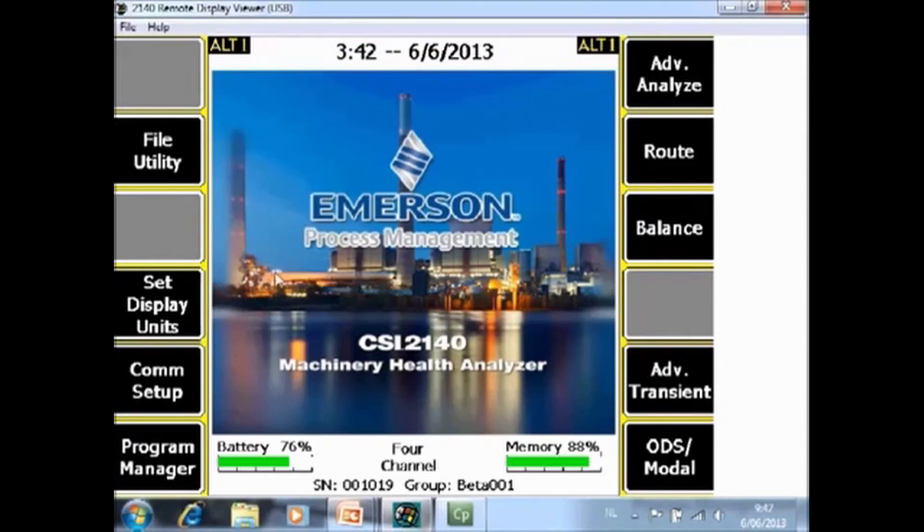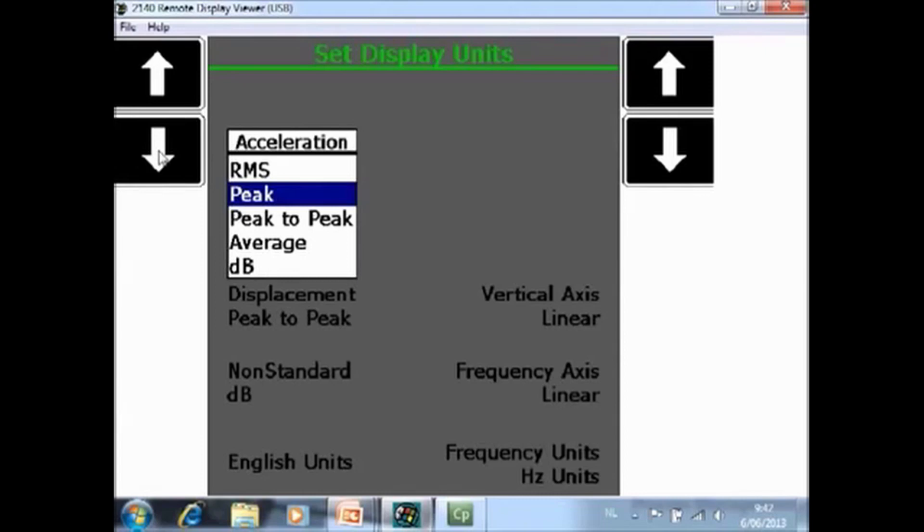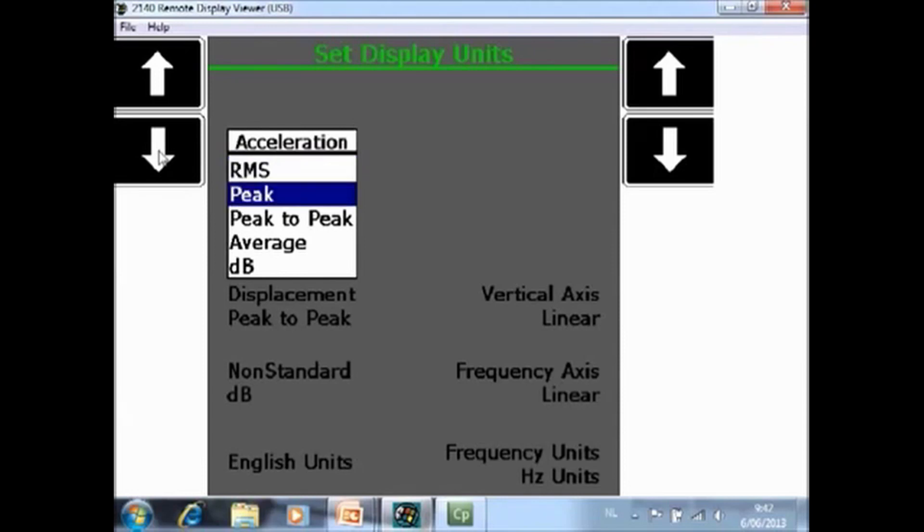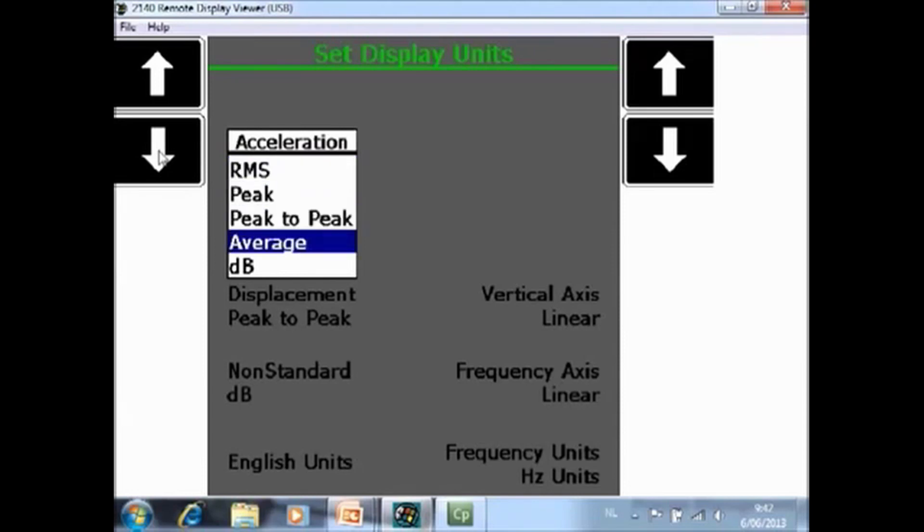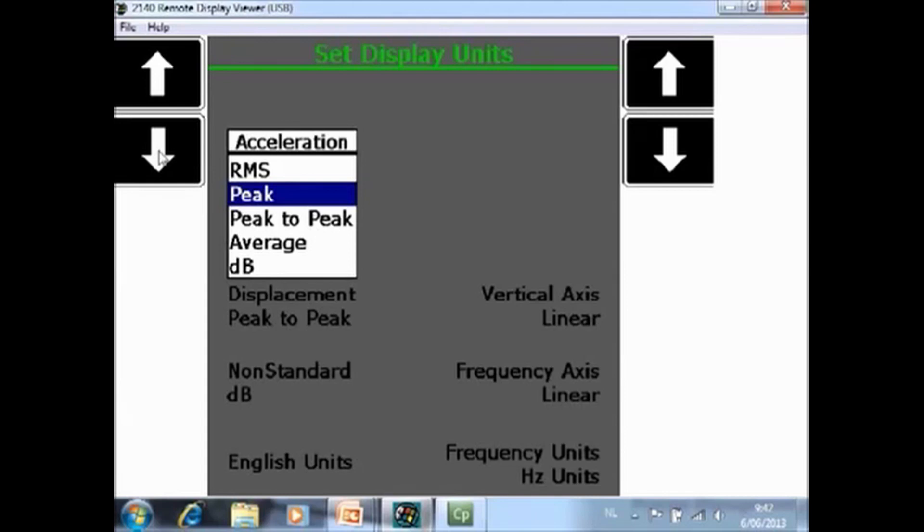F4 set display units. For F2 set acceleration you can specify here if you want to see your acceleration signal in RMS, in peak, peak to peak, average or dB. A special note here is that those factors will be applicable automatically and will even convert all your historically collected data already in the analyzer.